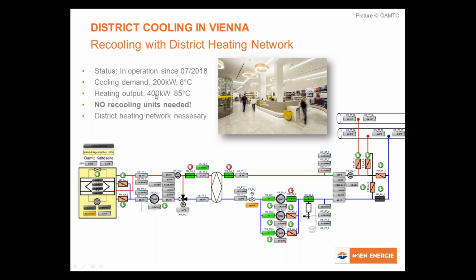We have a heating output of 400 kilowatts at 85 degrees. We don't need any recooling units; we do the recooling via district heating instead. So we actually have a combination of an electrical chiller and a heat pump, and we use the recooling from the chiller as a source for the heat pump. This way we use the recooling through our district heating network.